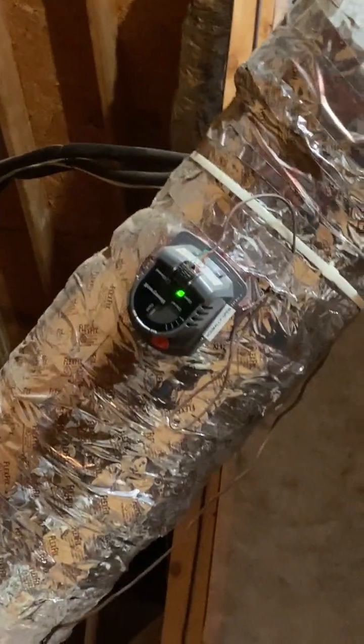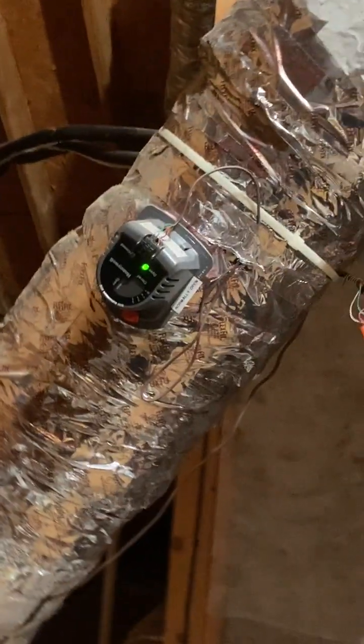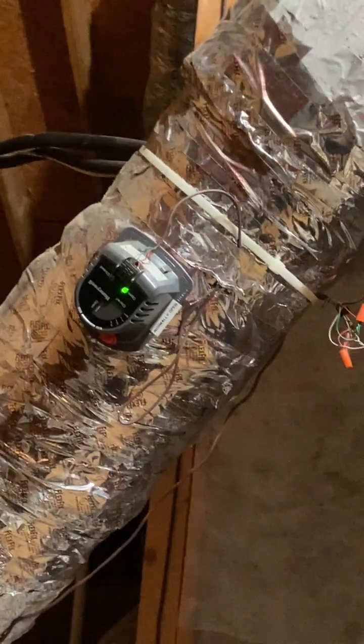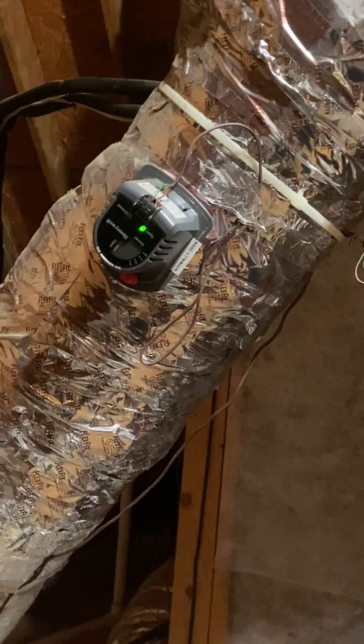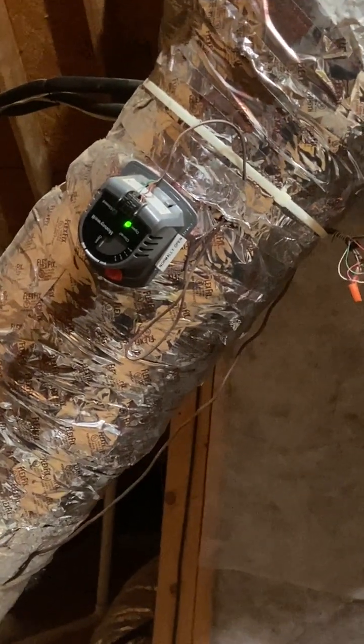And it's interesting. The first time I had a technician come because I had a problem, first thing he said was, well, we'll swap out all your zone control valves. They're old. Well, as far as I could figure out, they were all working. That was not my problem, okay? But in this particular zone, over time, I realized I did have a problem. Sometimes the thermostat would call for heat or cool, and I would get heat or cool in that zone, and other times not. And usually what I would do is take the thermostat off the wall, put it back on, and the zone would work. It turned out this valve, the old type valve that was here, was bad. And let me show you what this looks like.